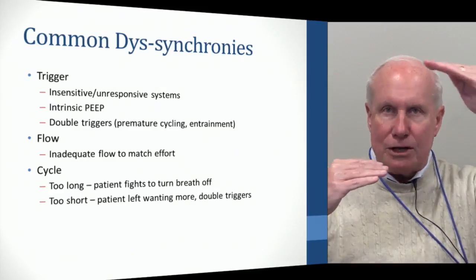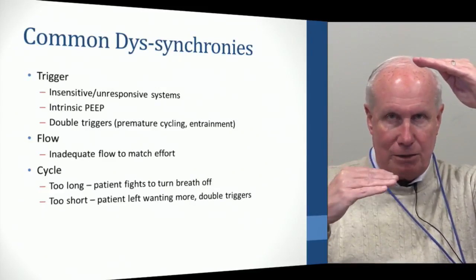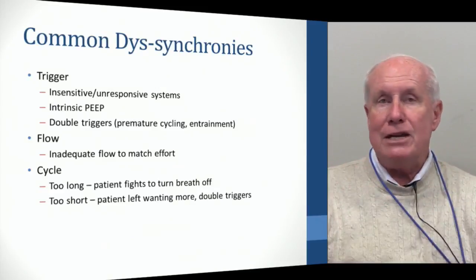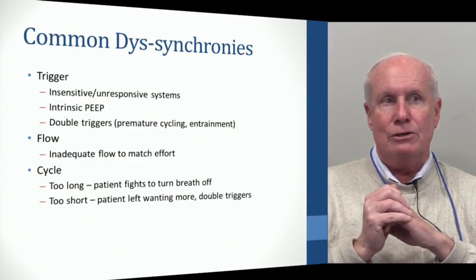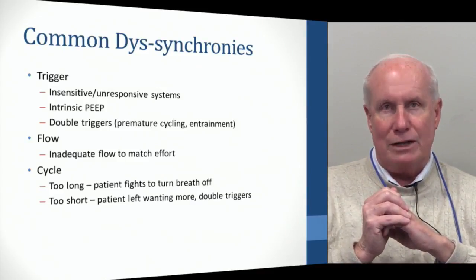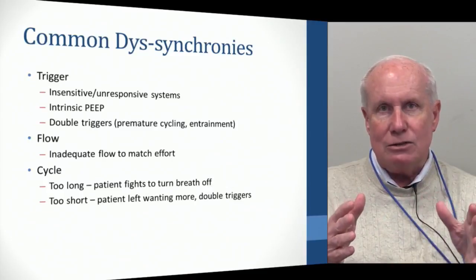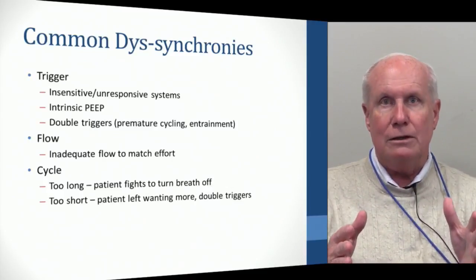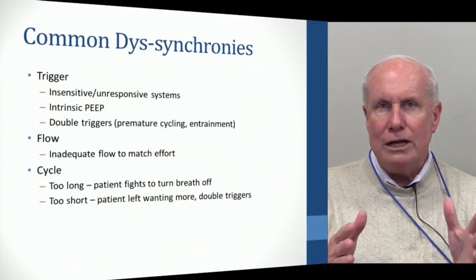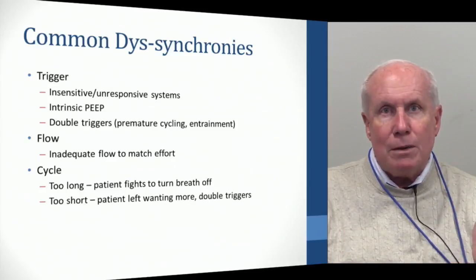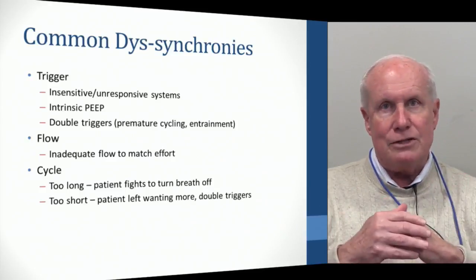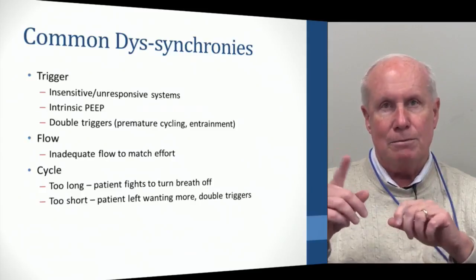So, alveolar pressure way high compared to circuit pressure puts a triggering load, and patients may not even be able to generate enough effort to trigger the breath. You get missed breaths. And you can sense this or see this by just looking at your patient. You'll see a patient who's pulling hard and the ventilator doesn't respond. Or if it does respond, it responds very slowly, a big lag, intrinsic PEEP.